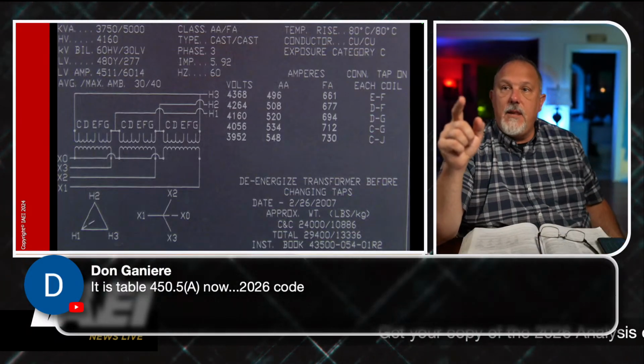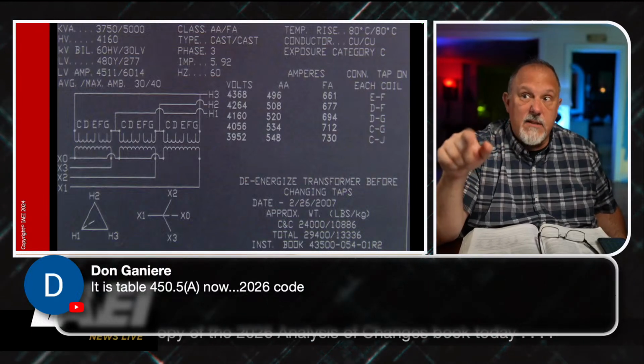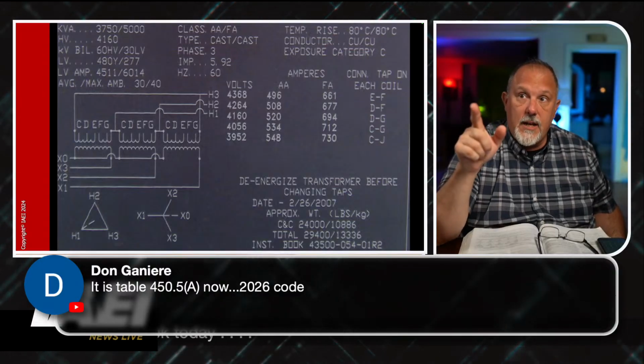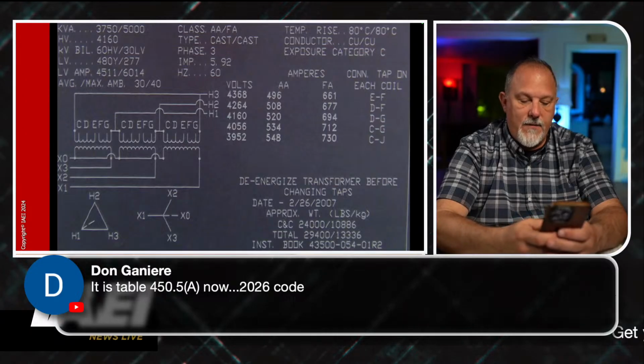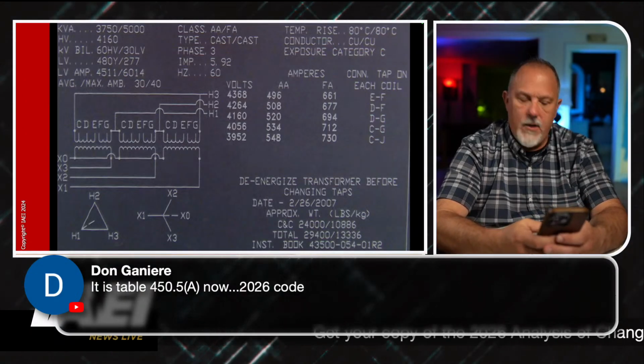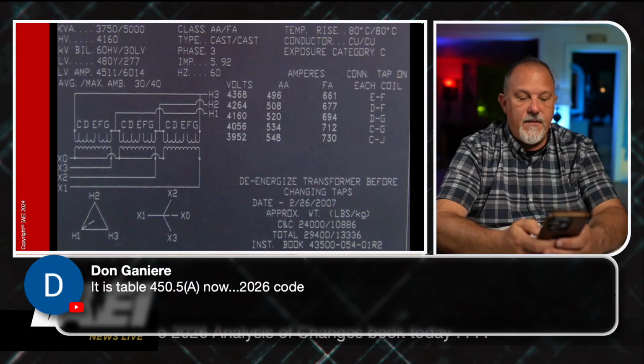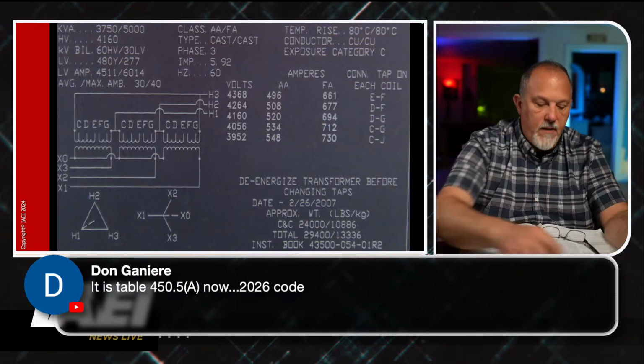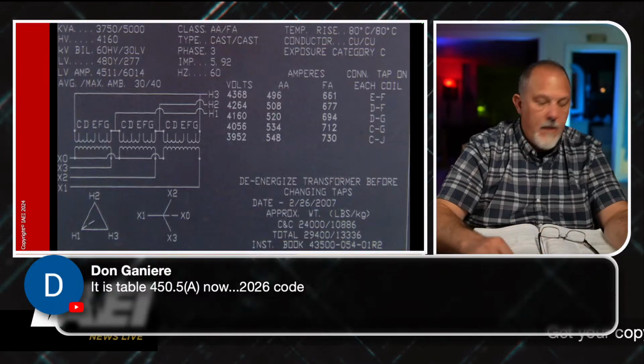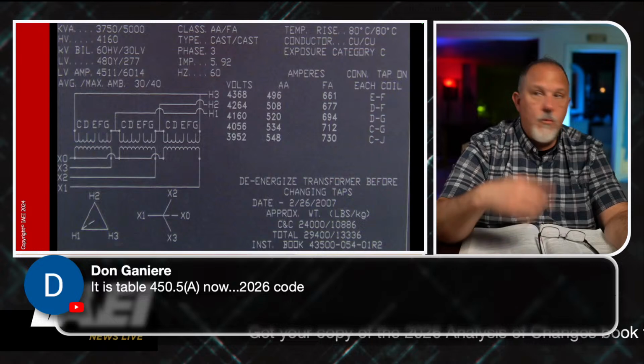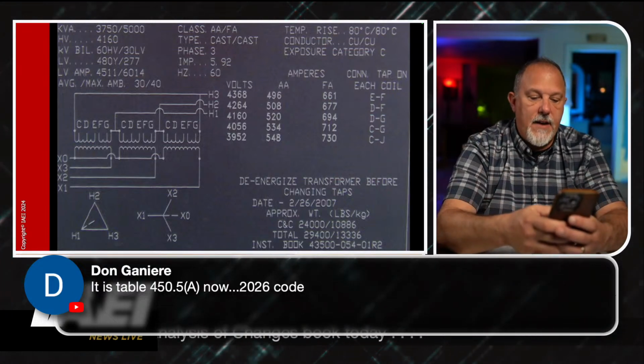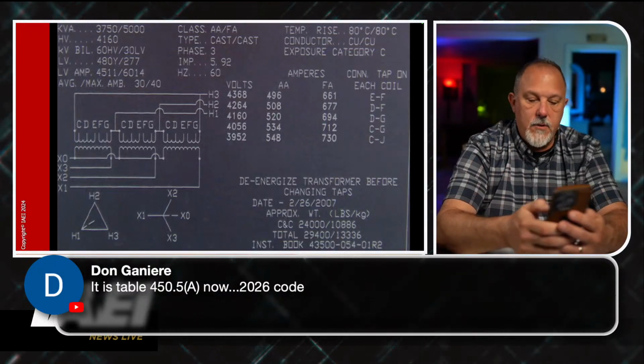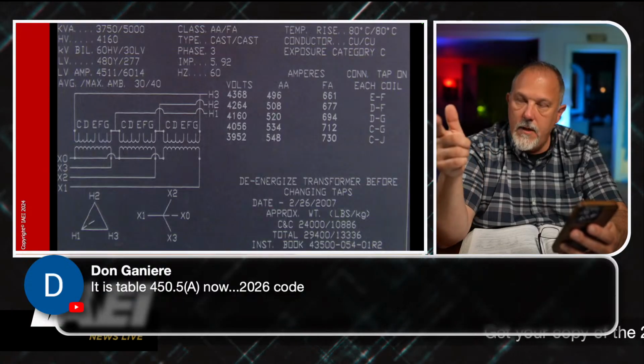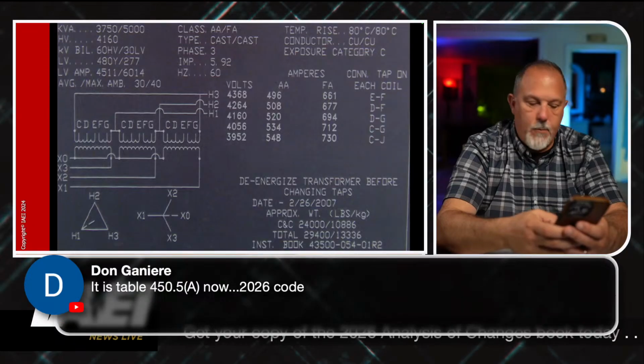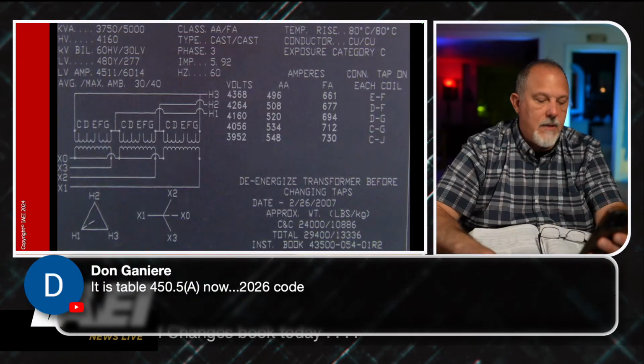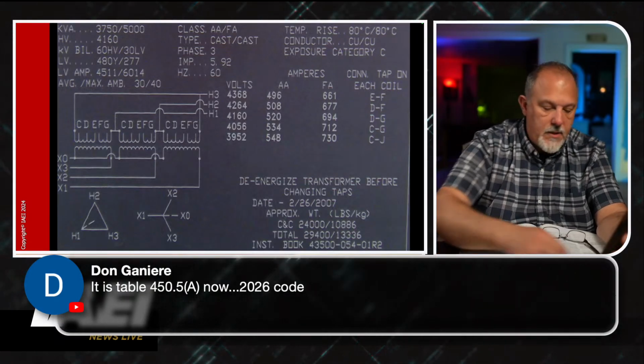Secondary, I'm going to be either 4,511 or 6,014. And that's on the nameplate, low voltage amps. Let's just do it. 3750 divided by square root of 3 divided by 0.48 is 4510.54. So they round it up. 4511 amps. And then we'll do the 5,000 kVA. 5,000 kVA, divide that by the square root of 3, divide that by 0.48. Boy, is 6,014. So that's the same. 6014 amps.